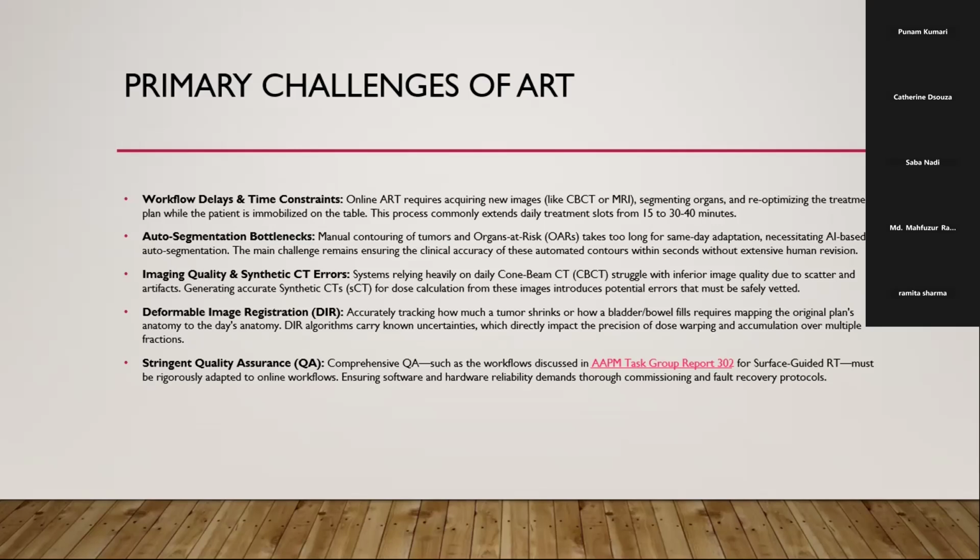Third one is the image quality and the synthetic CT errors. Systems relying heavily on daily CBCT struggle with inferior image quality due to scatter and artifacts. So generating an accurate synthetic CT for dose calculation from these images introduces potential errors that must be safely vetted.